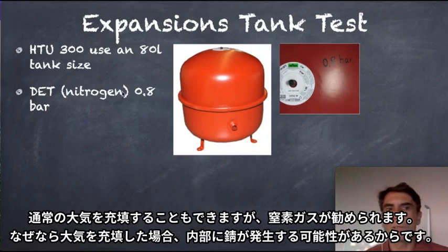Important actually is that we use the gas, so the nitrogen gas. If you use the usual air pump, you always get oxygen plus humidity inside. If you get oxygen and humidity inside, it can start to rust and it can damage the expansion tank. So the best is if you can use nitrogen gas.